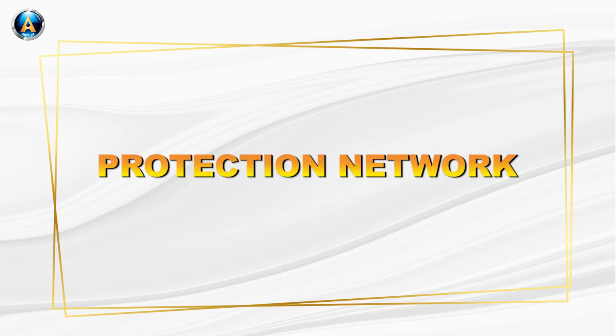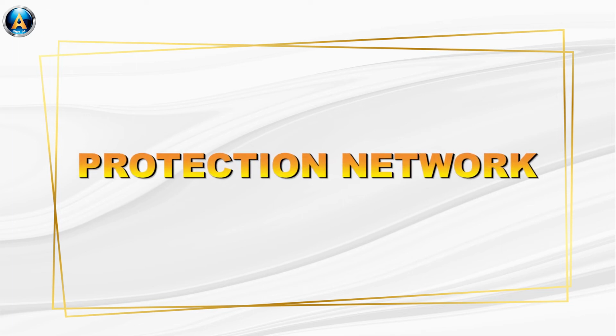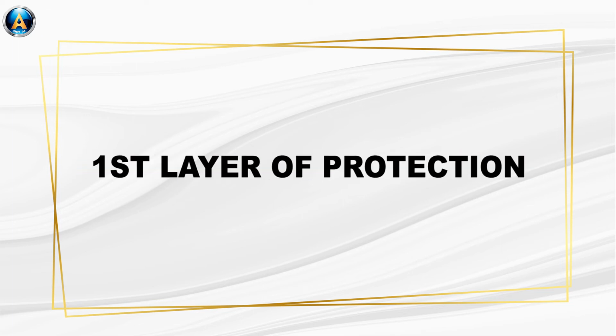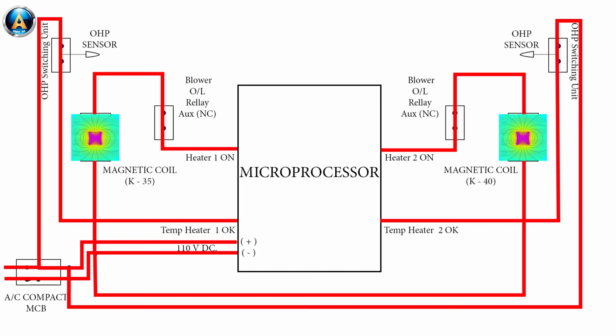Three layers of protection barrier are there in the heater network to avoid fire. The first layer of protection is controlled by the microprocessor, because whenever the inside coach air temperature stays above 21 degrees centigrade, then the heater coil may become inactive by the microprocessor, like this.